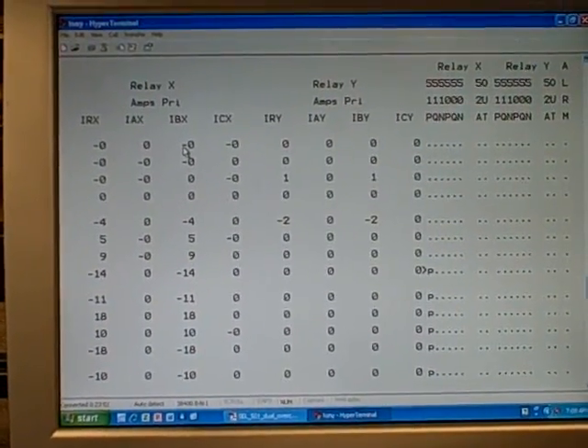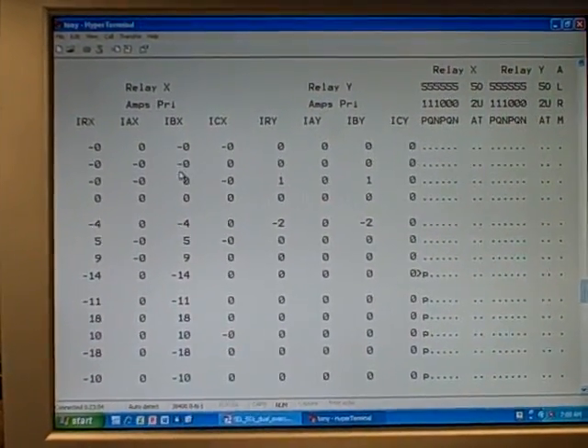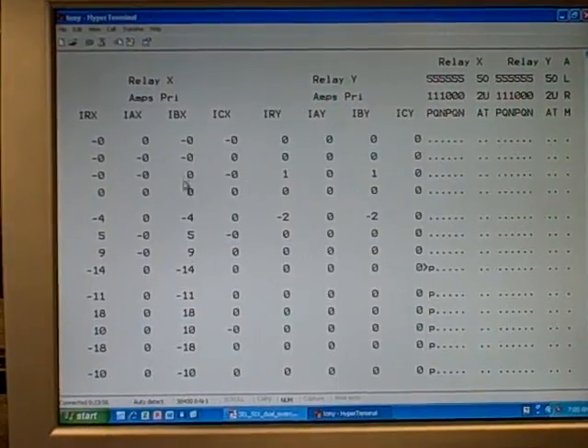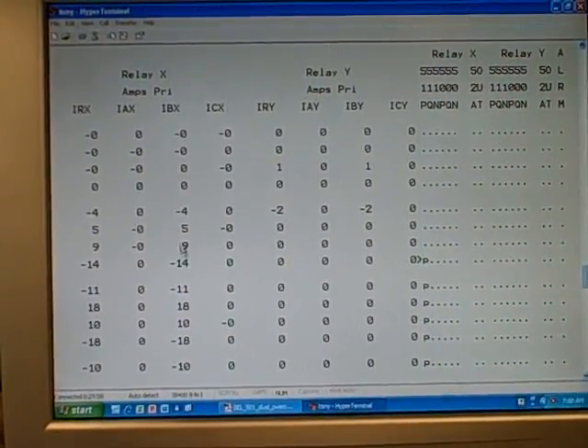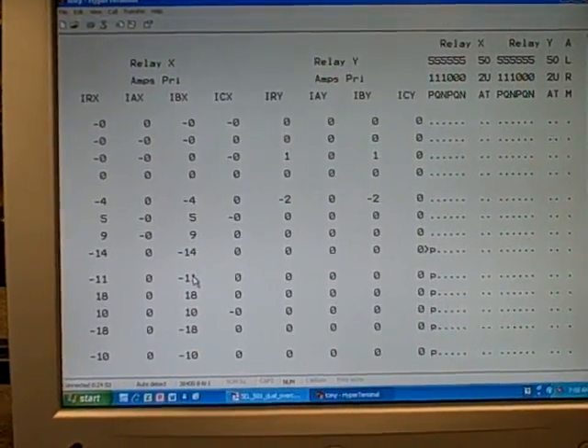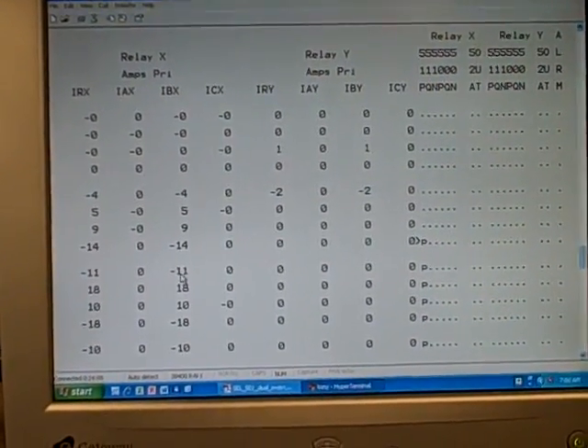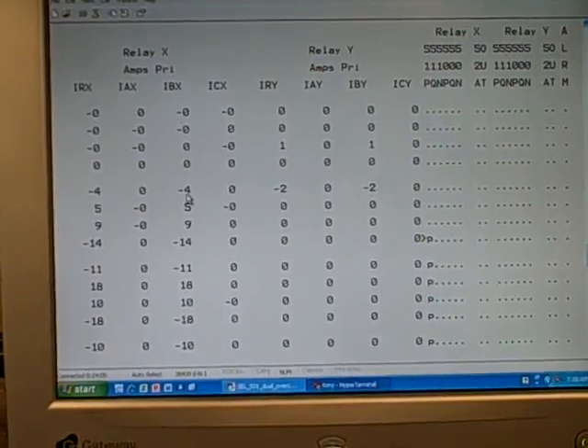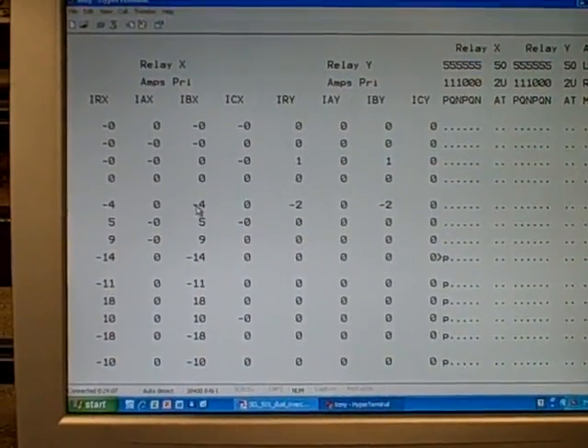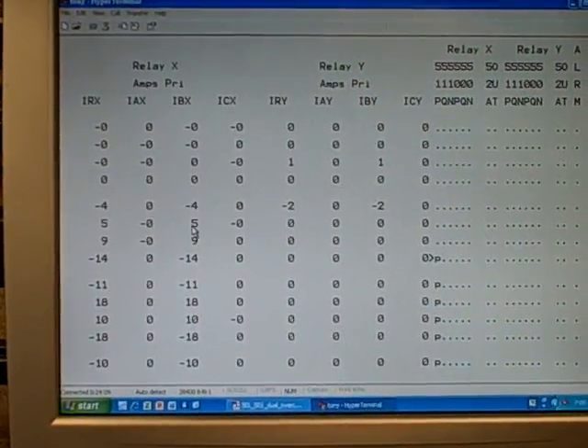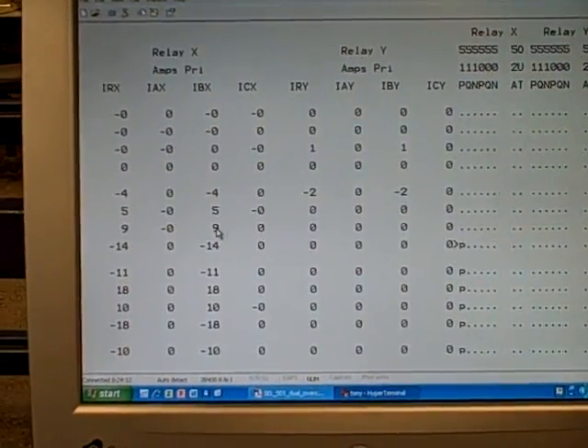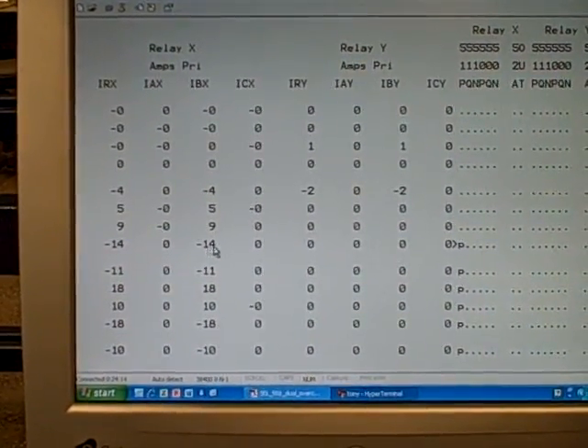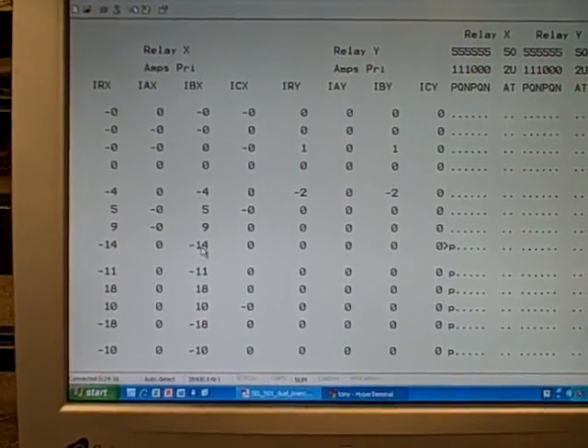What you see here are quarter cycle samples. So these four rows right here are one cycle of the AC wave. These four rows are another cycle of the AC wave. These four rows are a third cycle, etc. And these are instantaneous current values. So at this moment in time, minus 4 amps. This moment in time, plus 5 amps. This moment in time, plus 9 amps. This moment in time, negative 14, and so on.